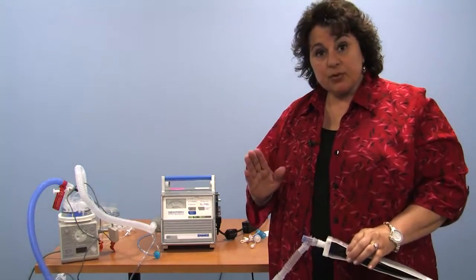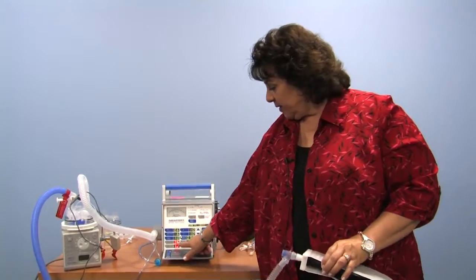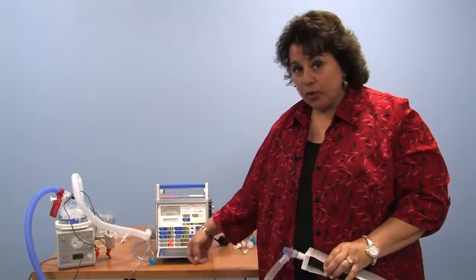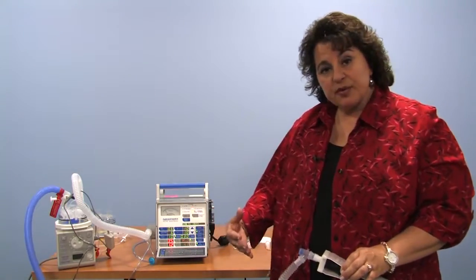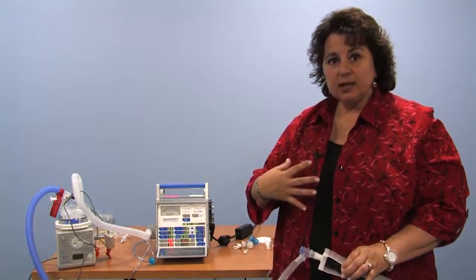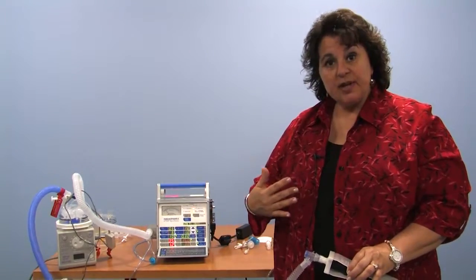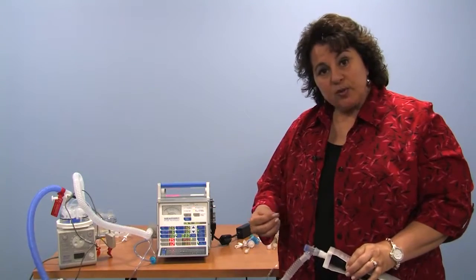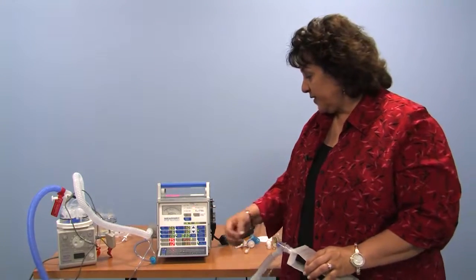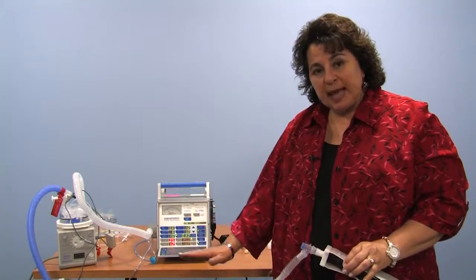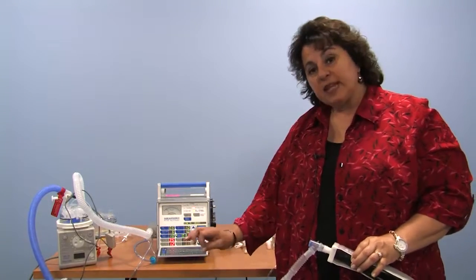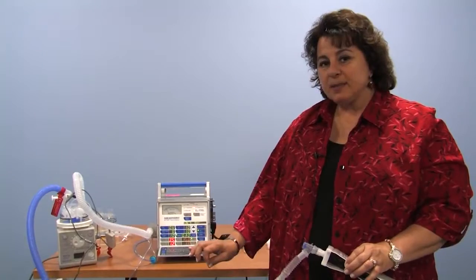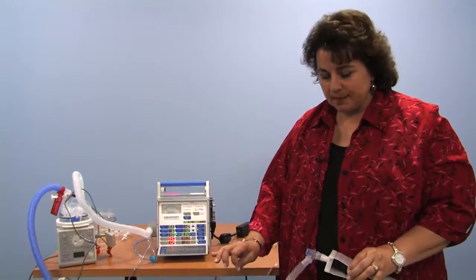We have high pressure alarm, currently set at 35 centimeters of water, which will audibly alarm if the pressure in the circuitry and potentially in your child's lungs reaches 35 centimeters of water. It will audibly and visually alarm. It'll reset itself if the condition, like one cough, goes away immediately. We also have the low pressure alarm, which currently is set at 12. If the 12 is blank, it means that in that particular mode on the HT50, it's preset by the machine. There's always a low pressure alarm.